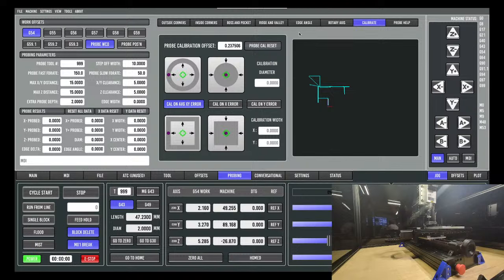So this one's interesting. I'll talk about this before we do the actual probe. To calibrate how much flex there is in the probe movement itself, you run these routines and you do it with a known dimension, and then it takes that measurement and calculates a value that corrects for the flex. You also need to enter the ball diameter as well when you're doing that.